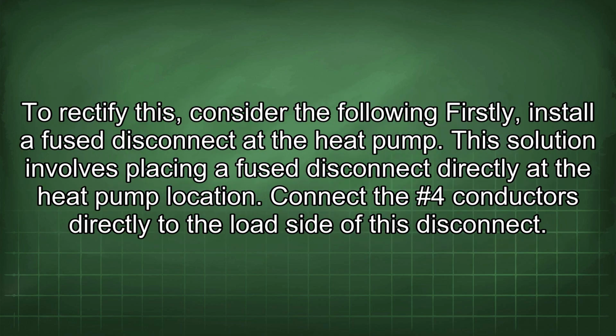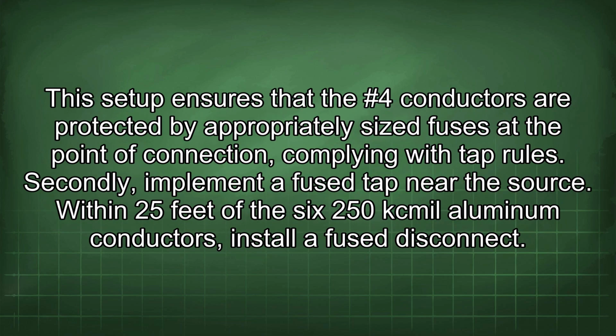To rectify this, consider the following. Firstly, install a fuse disconnect at the heat pump. This solution involves placing a fuse disconnect directly at the heat pump location. Connect the #4 conductors directly to the load side of this disconnect. This setup ensures that the #4 conductors are protected by appropriately sized fuses at the point of connection, complying with tap rules. Secondly, implement a fuse tap near the source.